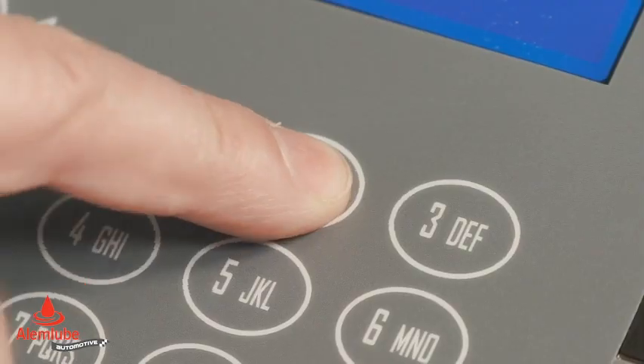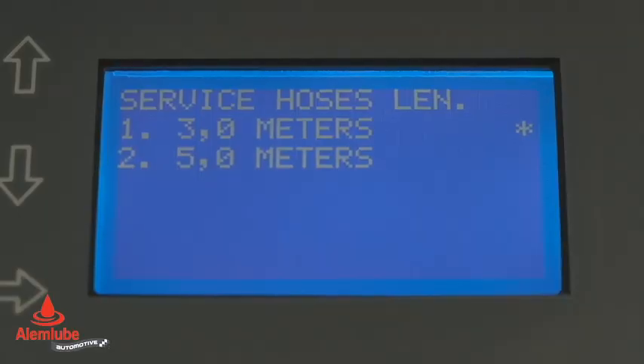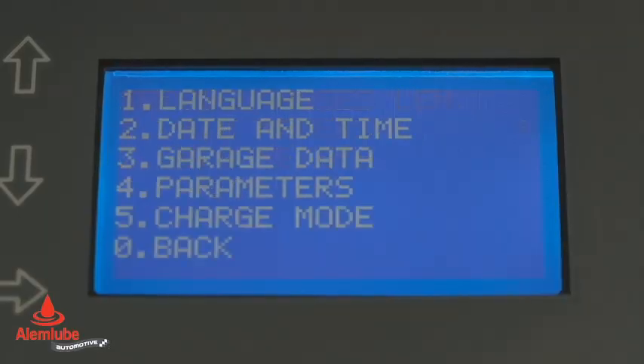Selecting 2 allows you to set the compensated charge mode and the tube length. In this mode, at the end of the charge, the pipes are directly disconnected because the software automatically compensates for the residual gas that remains in the pipes.